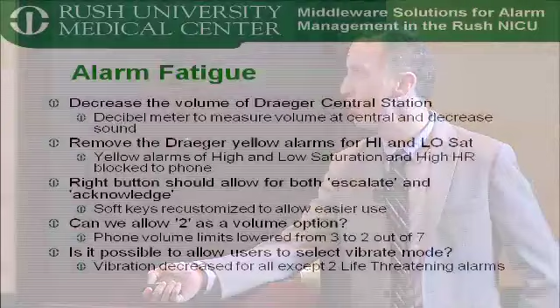The other thing we did was we noticed that all of these, what we call the yellow alarms, the high and low saturation alarms that are not the highest acuity, are really not actionable alarms, and people weren't doing anything about them. They would acknowledge it on their phone, or they would walk back over. The nice thing about the Drager monitor is there is that second level where if you drop another 10% below, you'll get a critical alarm. And so people weren't responding at all to the yellow alarms. So we thought, if nobody's responding to them, why bother having them go to the phone? And we just blocked those.